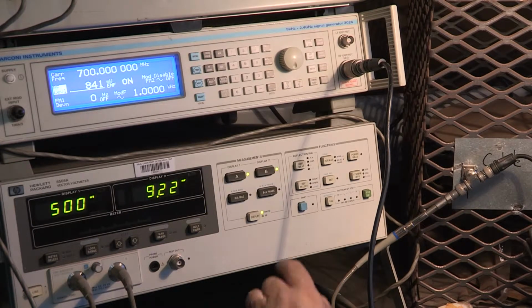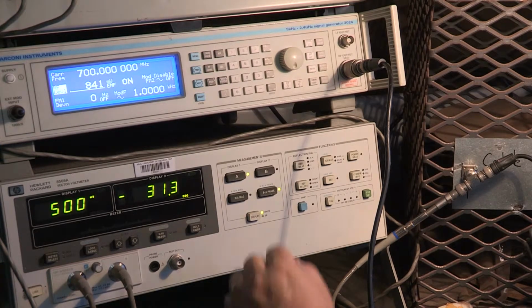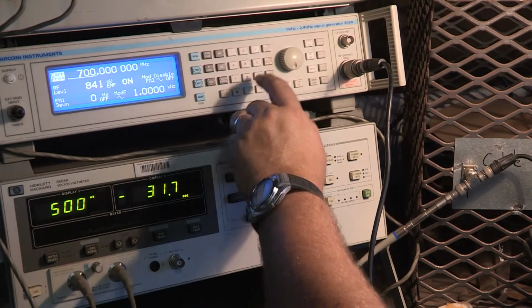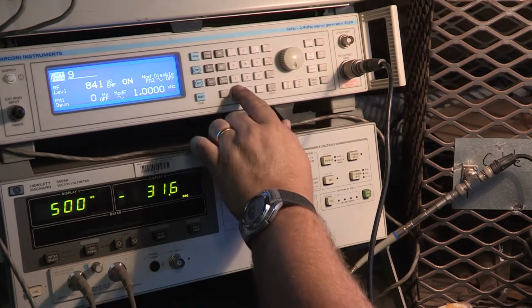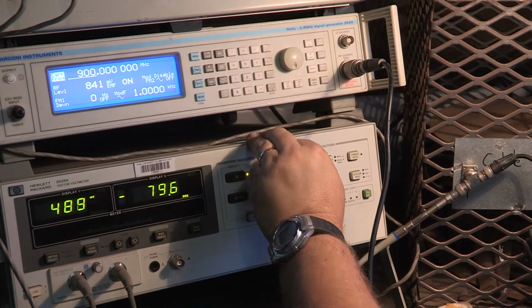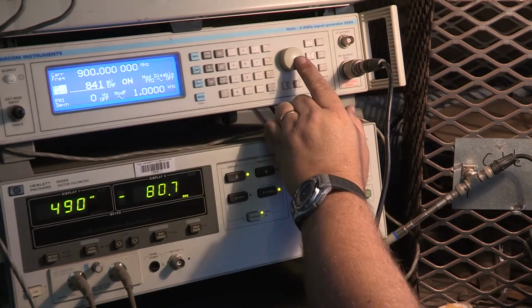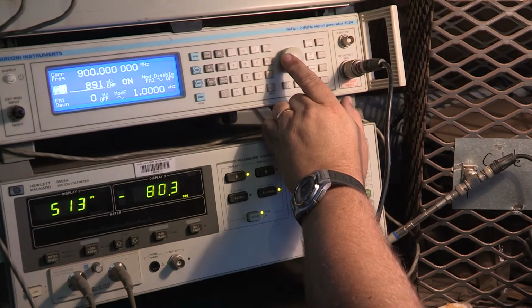9.21 millivolts, phase angle of minus 31.4. And we go to 900 megahertz. By the way, you can punch in the number as well. We'll jump immediately there.